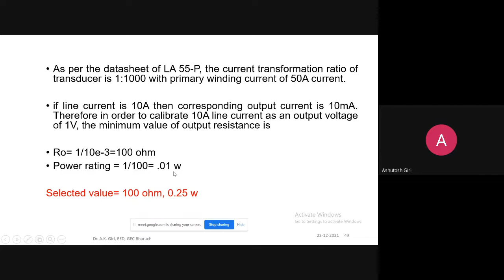That's why, suppose in our setup we are working with 10-15 amperes. If we are designing our sensor resistance value for 10 ampere, then the corresponding output current becomes 10 milliamps as per this transformation ratio. In order to calibrate 10 ampere line current as an output voltage of 1 volt, the minimum value of the output resistance will be calculated here, and the power rating is 0.01 watt. So the selected value is this.